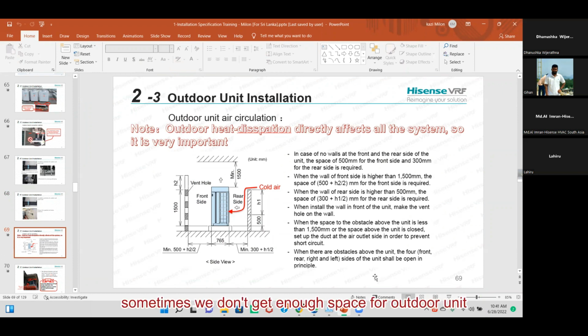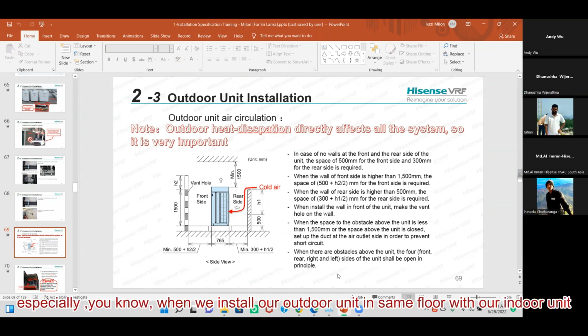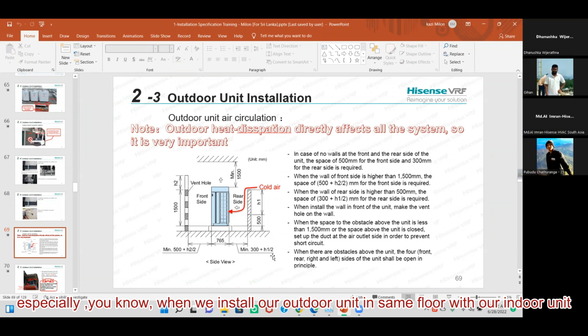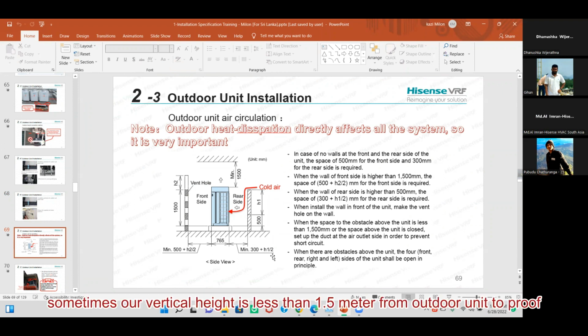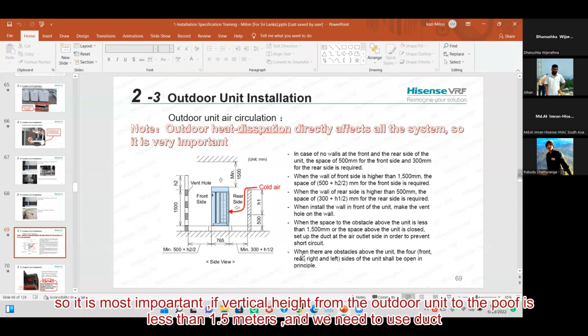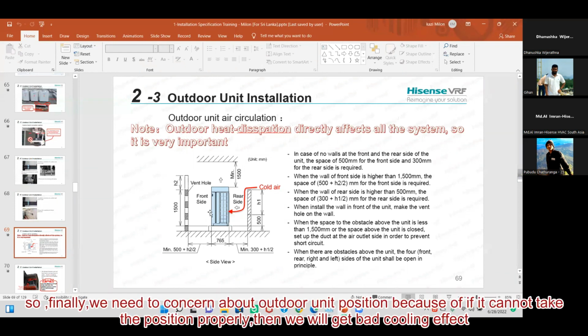Sometimes we don't get enough space for the outdoor unit, especially when we install our outdoor unit on the same floor as the indoor unit. Sometimes our vertical height from outdoor unit to roof is less than 1.5 meter. So it is most important: when our vertical height, outdoor unit to roof height, is less than 1.5 meter, then we need to use a duct. We need to use a duct. Finally we need to be concerned about our outdoor unit positioning, because if it cannot exchange heat properly, then we will get a bad cooling effect.